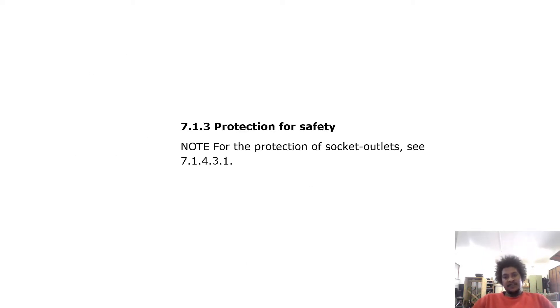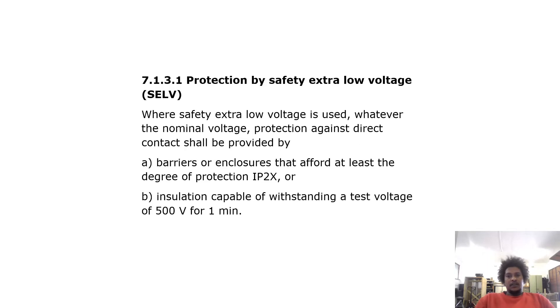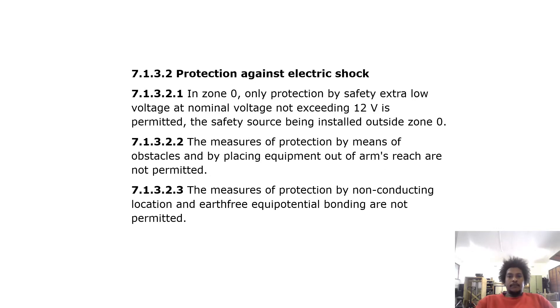Protection for safety — note for the protection of socket outlets, see 7.1.4.3.1. Protection by safety extra low voltage (SELV): where SELV is used, whether the nominal voltage, protection against direct contact shall be provided by barriers and enclosures that afford at least the degree of protection IP2X, or insulation capable of withstanding a test voltage of 500 volts for one minute.